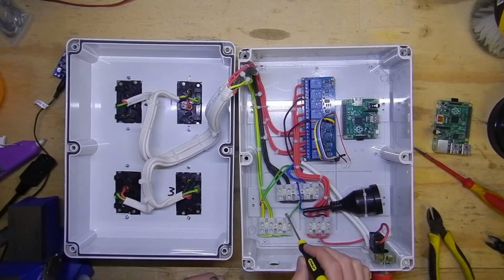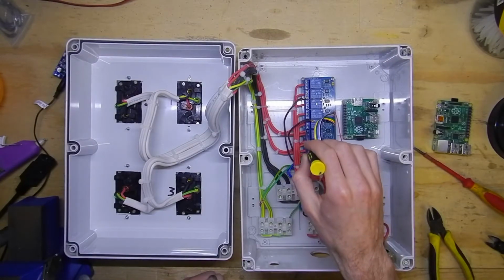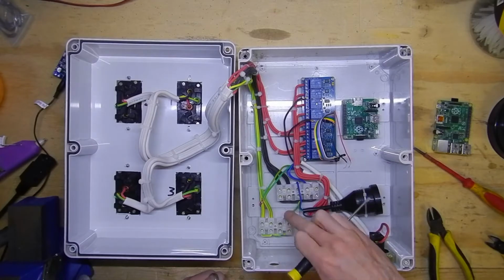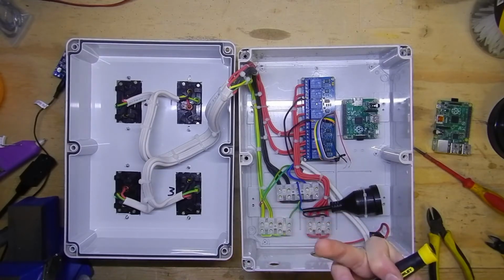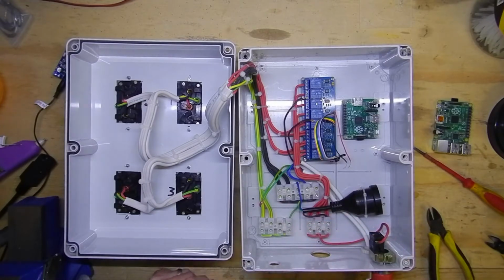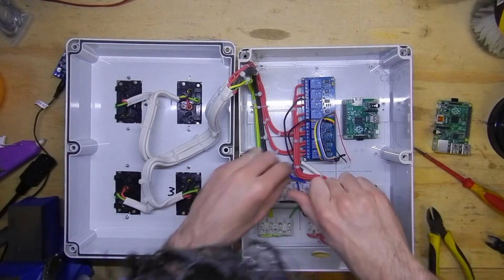Watch out for little guys like this. If that gets into your relays where the 240 volt is, that will cause you all sorts of lightning in the box, and we don't want to, as they'd say, let the pixies down the wire cause havoc. So just make sure you mop those up as you go along as well.